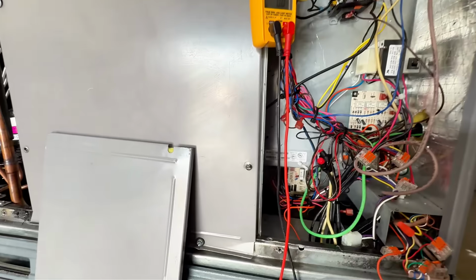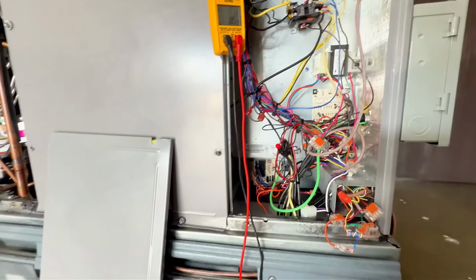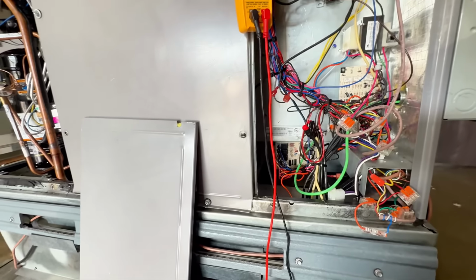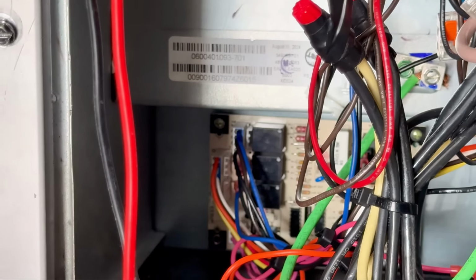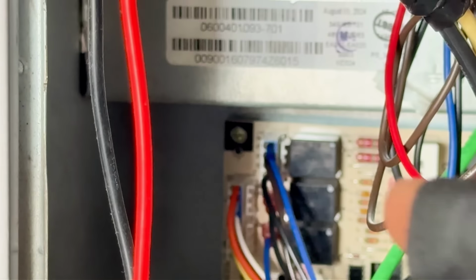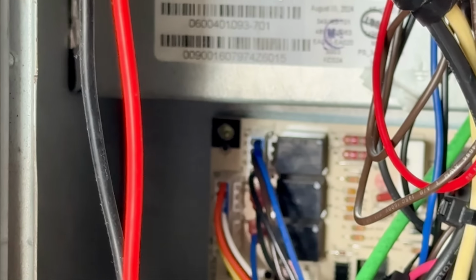Okay, so I see what he did. Once I connected it correctly, it had a little delay, and then it turned on. So that was the issue. Okay, that's interesting. So he did disconnect that right there on top. He plugged it in incorrectly, of course, on purpose. I know he did that on purpose. Let's see if you get a good picture of that. It's probably not better, but you see right there on top it says T2, but it was plugged in incorrectly, and now it's working. Now I'm getting 24 volts.